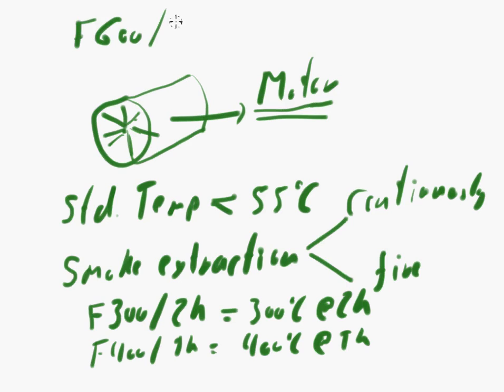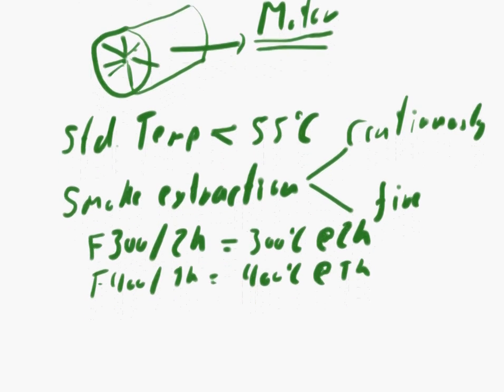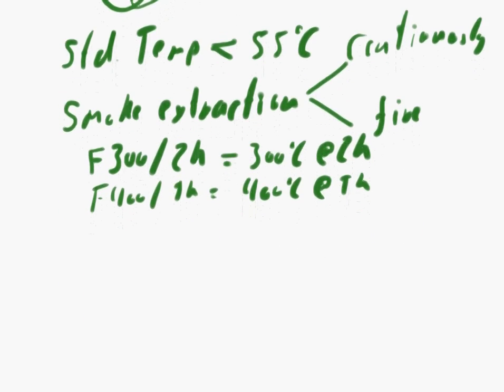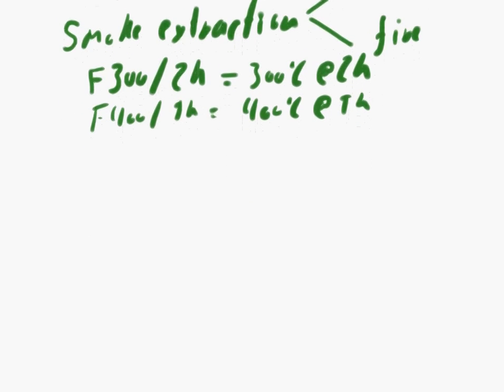Now, these fans are a bit special. And basically, with F600, you have some fans which can withstand 600 degrees, but these fans are a bit different. Here, no motor can withstand 600 degrees. So what they do is they have that motor, but that motor is isolated from the airstream.